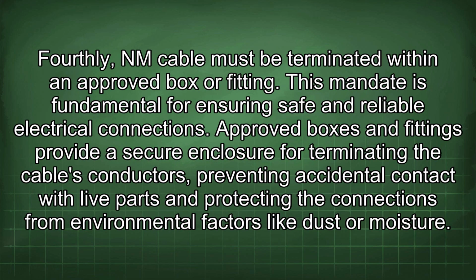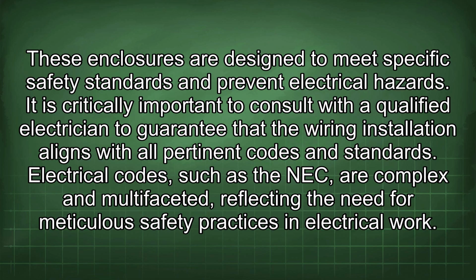Fourthly, NM cable must be terminated within an approved box or fitting. This mandate is fundamental for ensuring safe and reliable electrical connections. Approved boxes and fittings provide a secure enclosure for terminating the cable's conductors, preventing accidental contact with live parts and protecting the connections from environmental factors like dust or moisture. These enclosures are designed to meet specific safety standards and prevent electrical hazards.